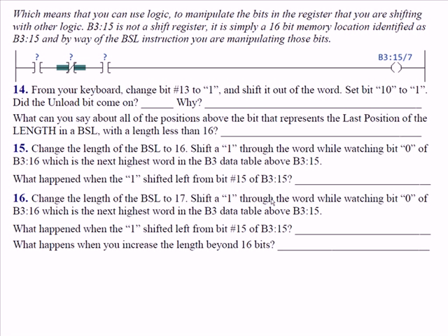That's how bit 7 could go to the on or the off state, because remember, an OTE instruction has a false and a true execution. So technically this rung of logic would control the state of bit 7. If the rung's true, bit 7 is going to be on. If the rung's false, bit 7 is going to be off. So be really careful. If you want to affect it one time, you need to use an OSR instruction, one shot rising, with everything that is a temporary state to the left of the one shot rising.